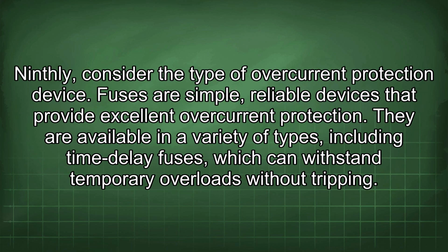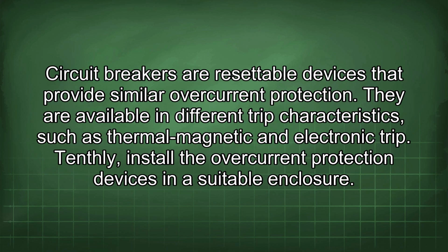Ninthly, consider the type of overcurrent protection device. Fuses are simple, reliable devices that provide excellent overcurrent protection. They are available in a variety of types, including time delay fuses, which can withstand temporary overloads without tripping. Circuit breakers are resettable devices that provide similar overcurrent protection. They are available in different trip characteristics, such as thermomagnetic and electronic trip.